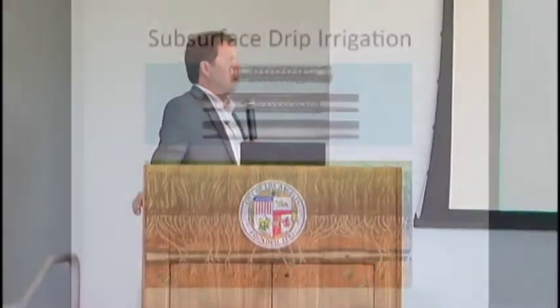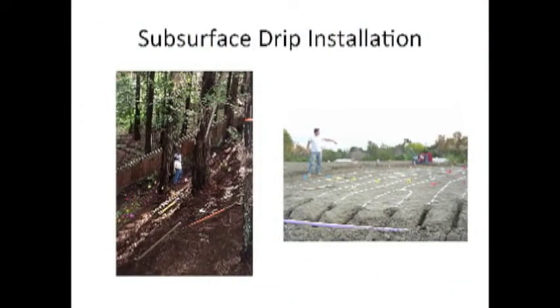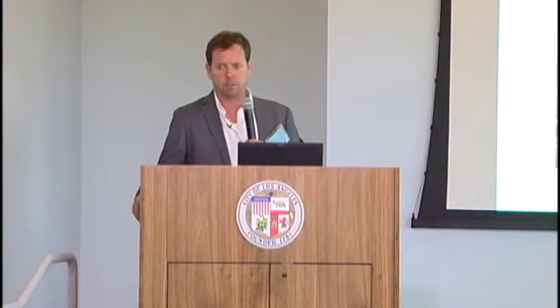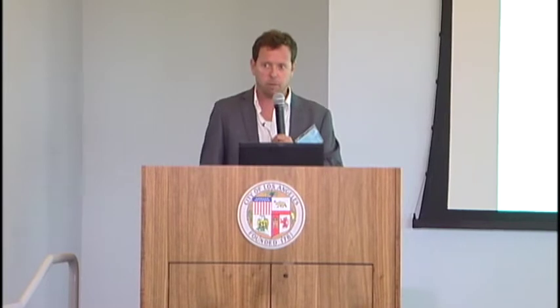I'm a strong proponent for subsurface drip irrigation. It allows a lot of flexibility and is a little bit of a challenge from a design standpoint, but when reusing water, it meets the requirements of the code very effectively. There are a number of companies that make different products, and it does have to be buried. If it's treated black water, the subsurface drip line has to be buried 12 inches below grade; otherwise it's considered Title 22. With graywater or stormwater, they're substantially more flexible — only two to three inches of cover is required, and mulch counts as the cover.